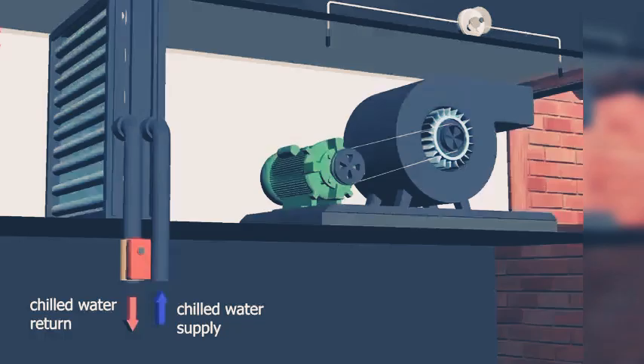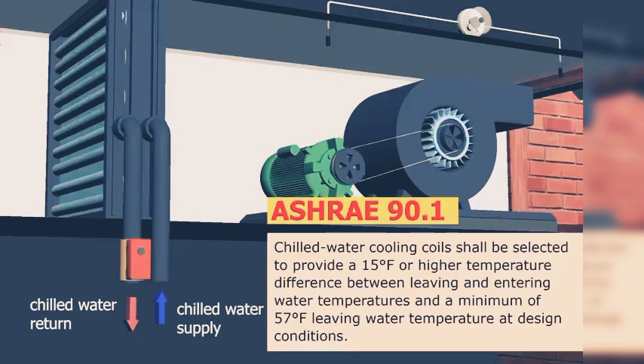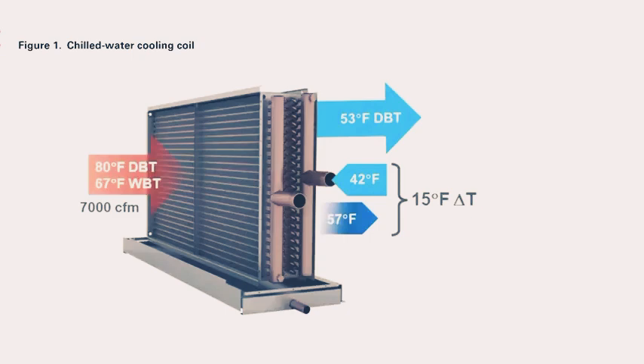Beginning in its 2016 version, ASHRAE Standard 90.1 now requires chilled water cooling coils be designed for at least a 15 degrees Fahrenheit temperature difference between the leaving and entering water. And the leaving water temperature must be no colder than 57 degrees Fahrenheit, at design conditions. As an example, for the leaving water temperature to be 57 degrees Fahrenheit, the coil in Figure 1 is selected with a 42 degrees Fahrenheit entering water temperature. This would comply with the minimum 15 degrees Fahrenheit delta T requirement.